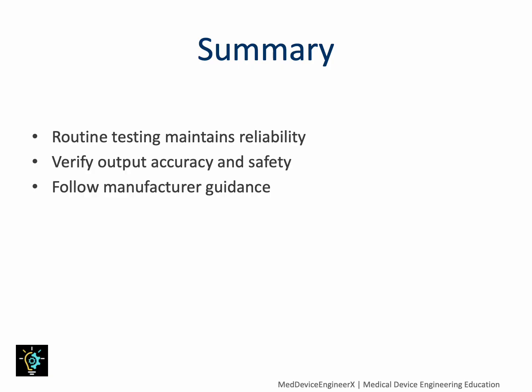Every maintenance session ends with confirmation. The FT10 must perform safely, deliver accurate energy, and meet all electrical standards. Regular testing identifies small faults before they affect patient care. If a reading falls outside tolerance, recalibration or service intervention is required. Consistent testing isn't just regulatory, it ensures reliability, accuracy, and the continued trust placed in the surgical system.